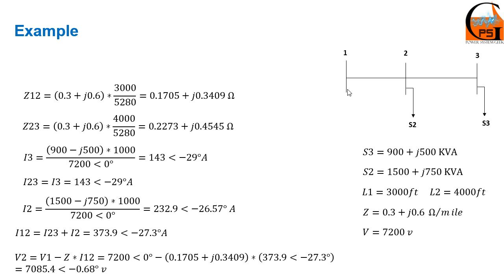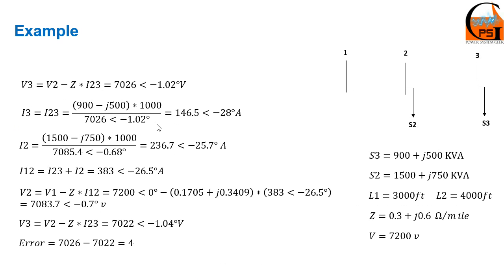Now we do the forward sweep and calculate the voltages of each bus. We have the voltage for the first bus, and we calculate the voltage for the second bus using the KVL formulation: V2 = V1 minus Z12 times I12. We do the same for the third bus using the voltage we just calculated for the second bus: V3 = V2 minus Z23 times I23. We have now reached the end of the feeder and the first iteration is complete.